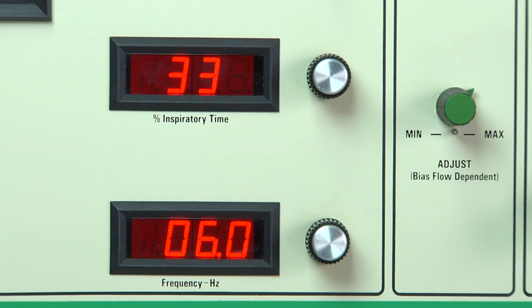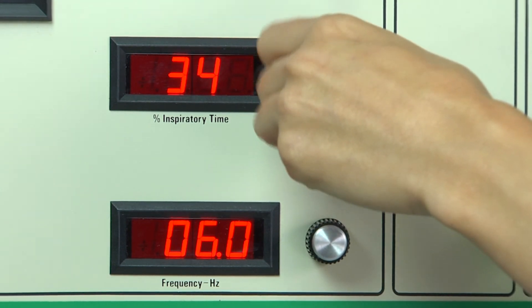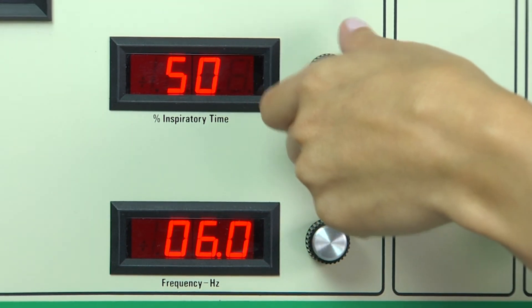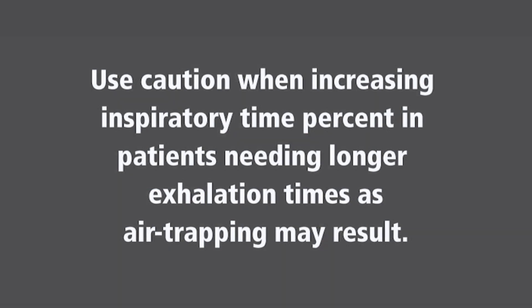Inspiratory time percent sets the relative duration of the successive positive and negative polarity voltages from the square wave driver. Since this parameter is set as a percent of cycle time, absolute inspiratory time is a function of oscillatory frequency and inspiratory time percent. For most applications, this parameter remains at 33%. In applications where the patient presents with refractory hypercapnia in the face of maximum ventilatory support, increasing the inspiratory time percent may improve ventilation and lung recruitment. The effect is most pronounced at lower frequencies. Use caution when increasing inspiratory time percent in patients needing longer exhalation time, as air trapping may result.